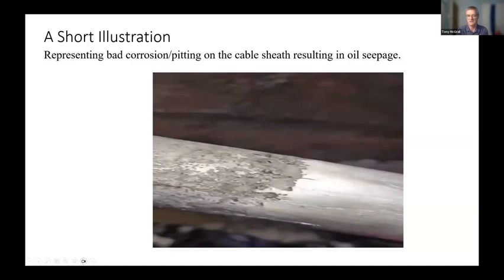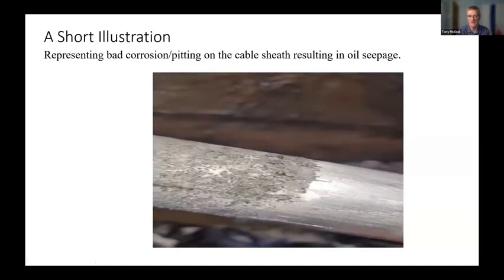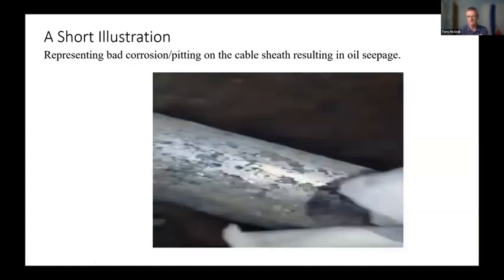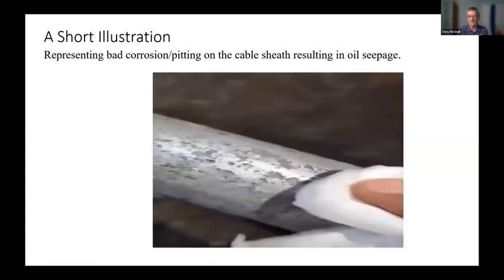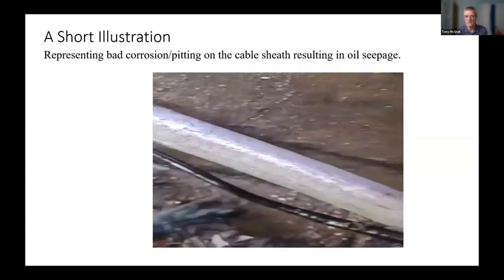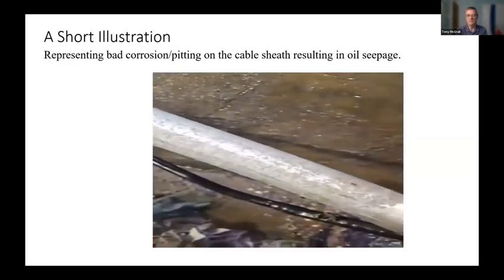In this case, this pitting was caused by the direct bury, and on a 275 kV cable, you do have a PVC wrap around that, but it still does have that problem occasionally within the cable. Cable sealing ends are the far more likely failure mode, but they've got problems. In this case, we had a save and everyone was happy.